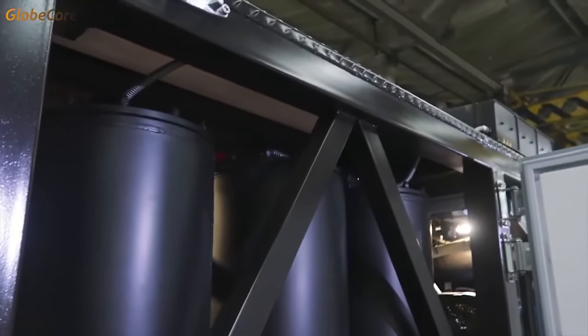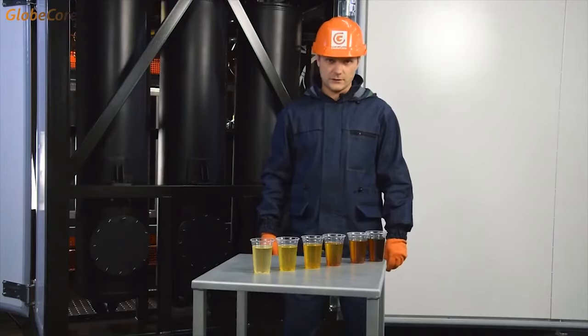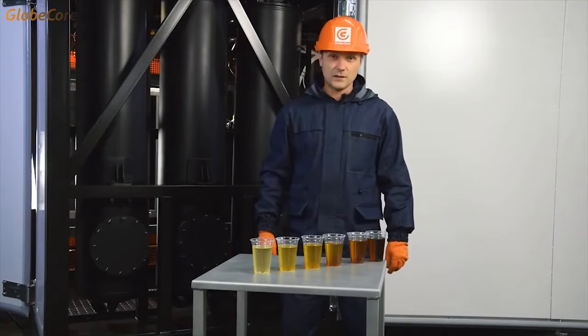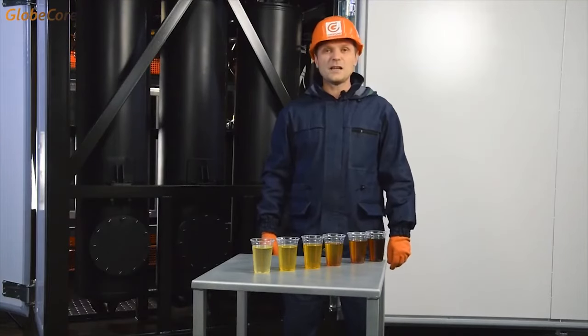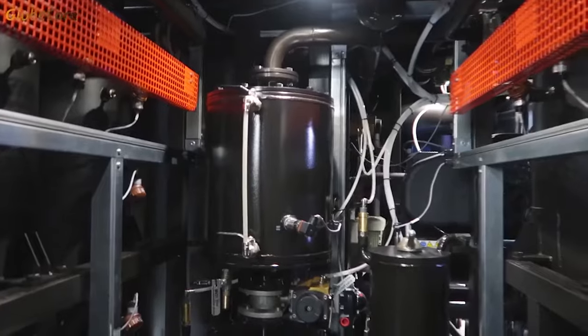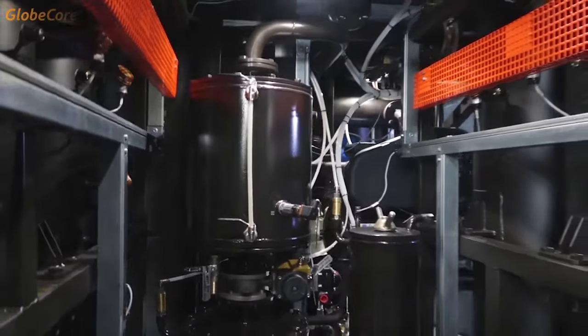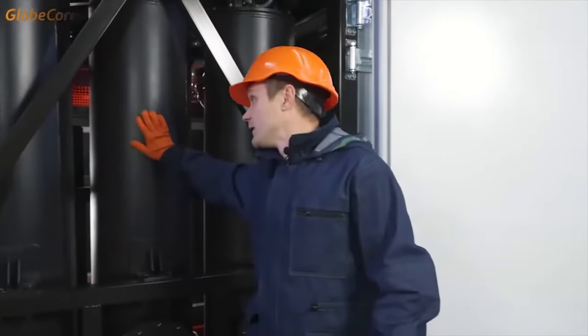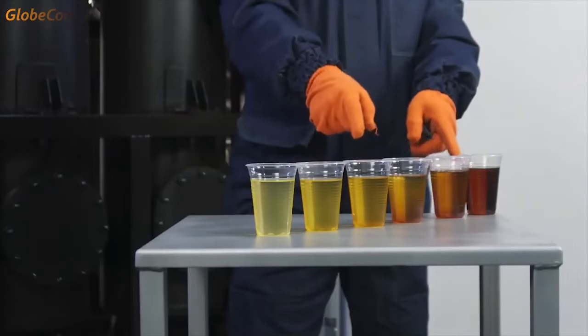It is very important to note that the sorbent can be reactivated hundreds of times without any loss of process quality. It is also notable that the process requires no extra handling of the sorbent and occurs directly in the regeneration columns. As soon as the quality of the processed oil becomes unsatisfactory, the reactivation process can be started.